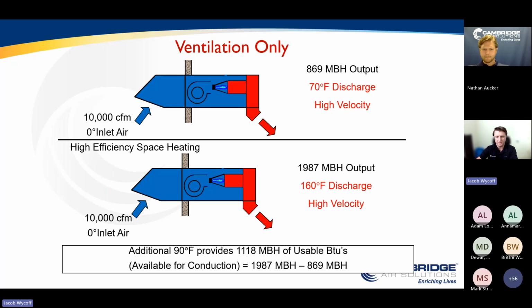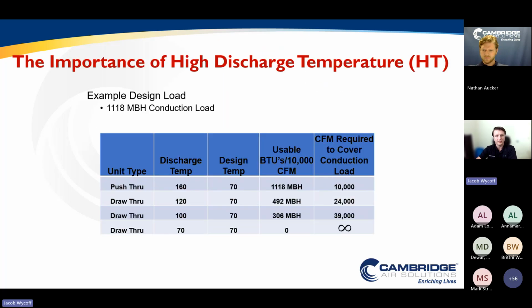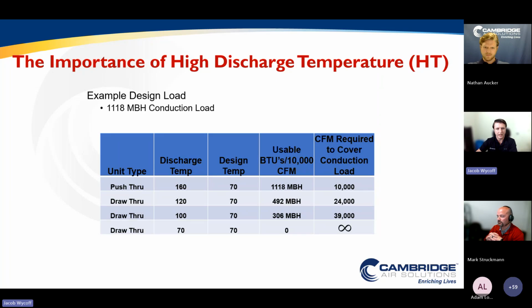It's going to give us 1100 MBH of BTUs that are usable to cover the conduction losses of the space. So this slide right here does a great job of really showing the high importance of high discharge temperature. Take that example where we have an 1100 MBH conduction load of the space. If we allow ourselves to discharge at 160 degrees, we know we're only using 10,000 CFM to cover that conduction load. But if we have a draw-through style unit where we're restricting the discharge temperature down at 120 degrees, now it's going to require 24,000 CFM of outside air to be able to cover that heat load because we're only getting 492 MBH of usable BTUs per every 10,000 CFM that we provide.